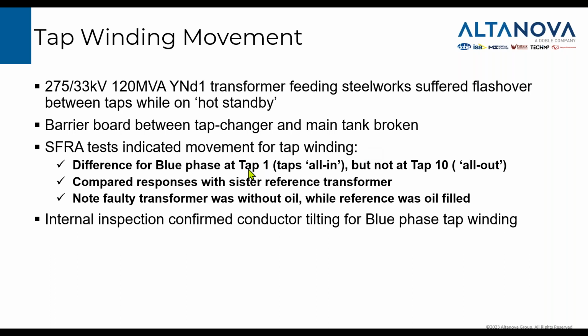And so here, a little comment about that. It was found on tap 1 where all taps were in, but not on tap 10, which was the nominal tap position, or actually the middle tap position, with all the regulating winding out of circuit. So this test, as proposed in the IEC standard, is one of the tests to do with all taps in and all taps out. This test helps us identify that the problem is located inside the regulating winding. We had reference responses from a sister transformer. The only problem was that the faulty transformer was without oil, while the reference was oil filled.